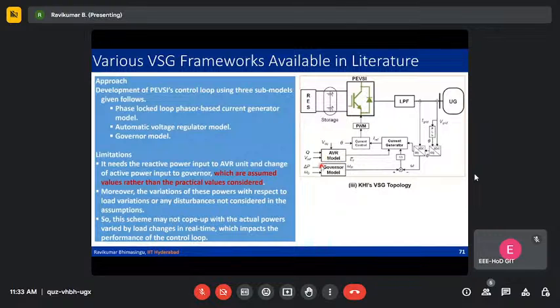This topology also requires information such as Q, omega naught, V reference, and delta P, which are assumed values rather than practical values. Moreover, the variations of these powers with respect to load variations or any disturbances have not been considered in these assumptions, so the scheme may not cope up with the actual powers varied by load changes in real time, which impacts the performance of the control loop.